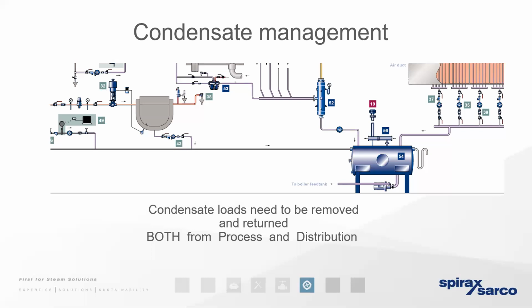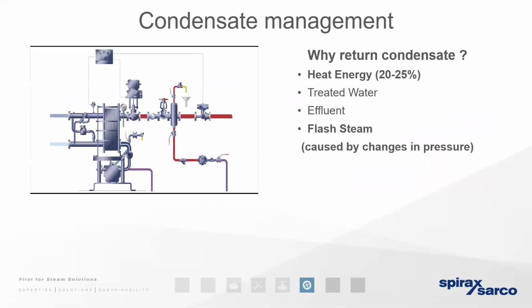So we know that we need to remove the condensate and take it away from the network, but we also know that it does have a value if we can return it back to the hot well. Remember, condensate is water. Water's got a specific heat capacity of 4.19. Therefore, if the condensate exists at 0 bar gauge, we know that water and steam have got a similar temperature, 100 degrees C. So if we multiply 100 by that 4.19, that tells us that every kilogram of condensate has got 419 kilojoules of energy contained within it. If we can return that to the boiler house, well, it's 419 kilojoules of energy that we're potentially saving if we were bringing the water up from 0 degrees to start producing steam again.